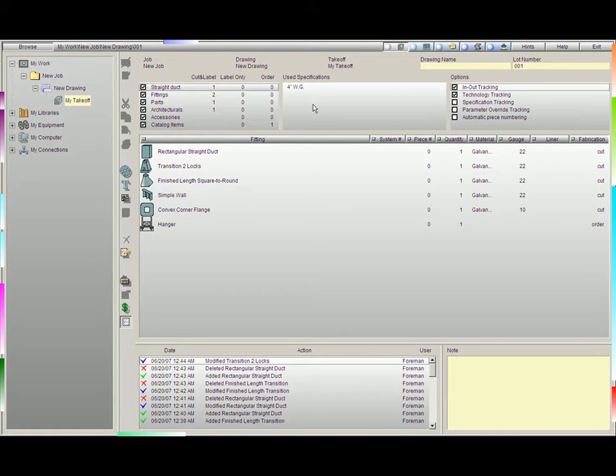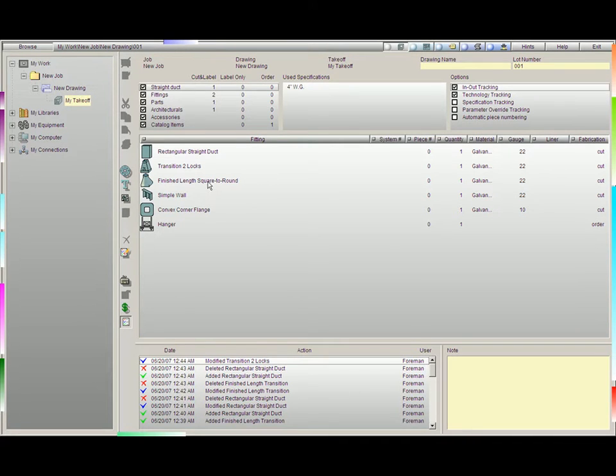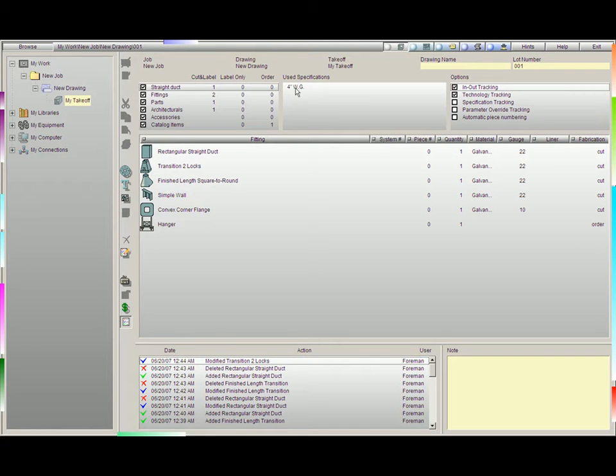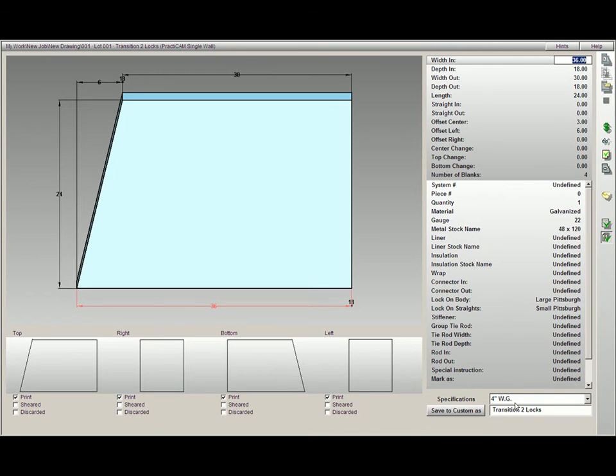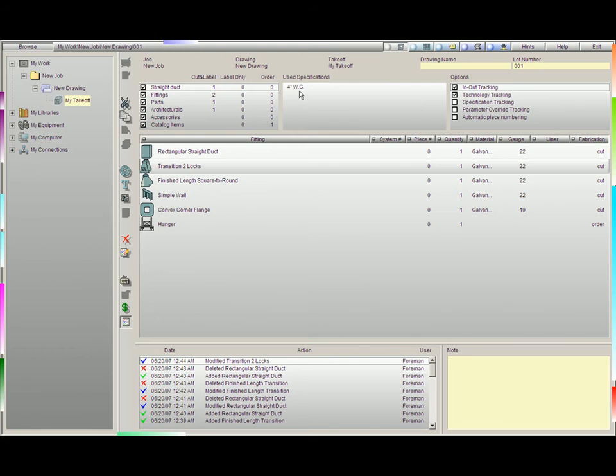The next box here is the used specifications. Every time one of these fittings or pieces of duct has a specification table that we use, we're going to mark it here. You'll notice that my transition with two locks has a 4-inch water gauge specification table applied to it. You can see us tracking that 4-inch water gauge specification table right here.